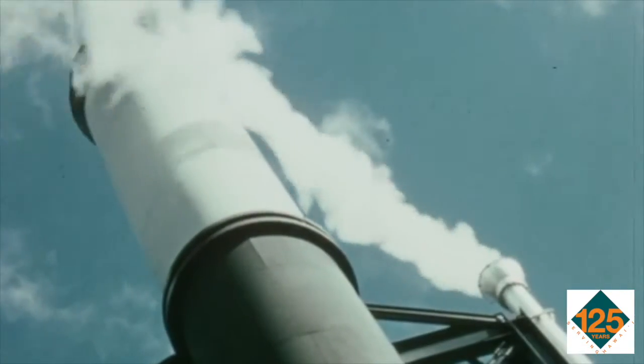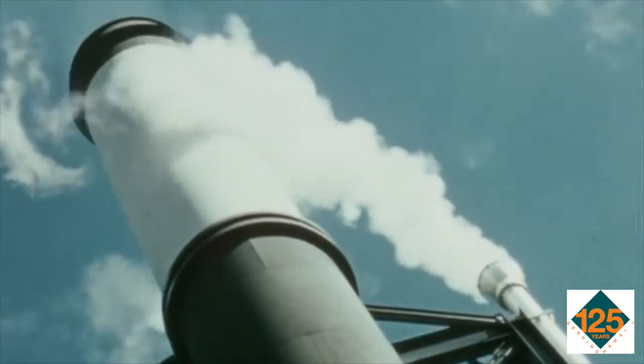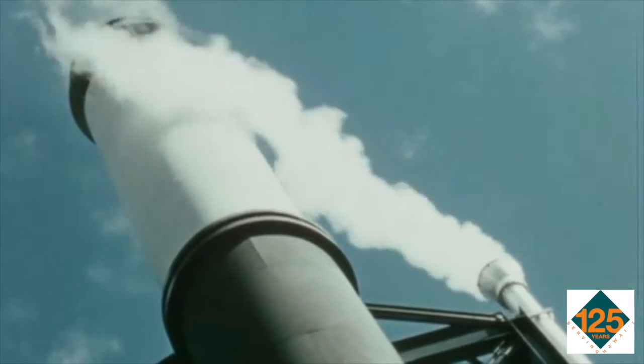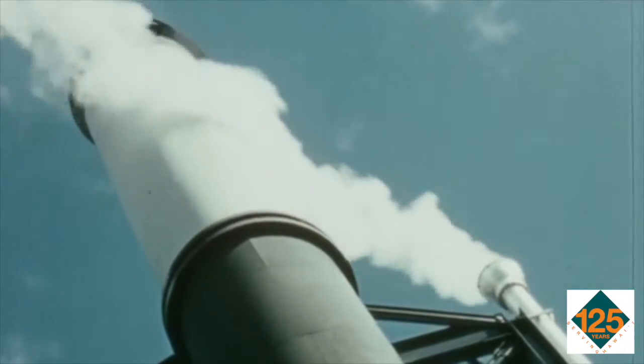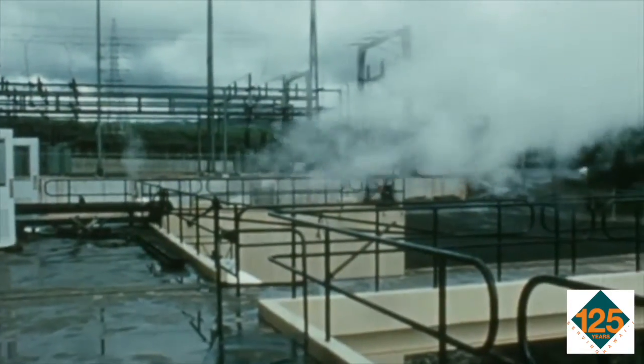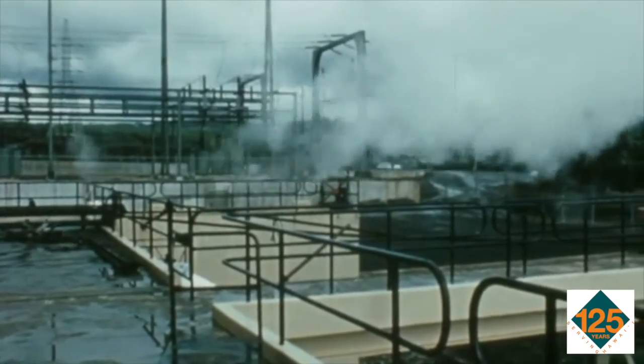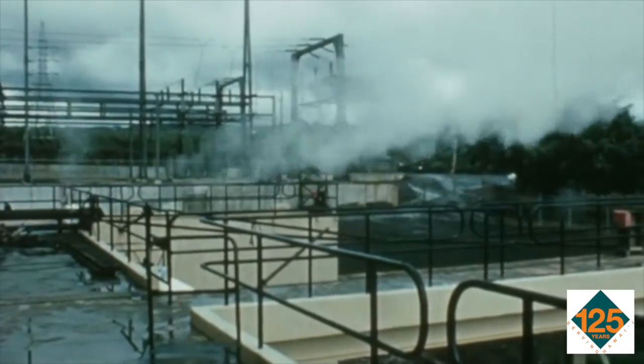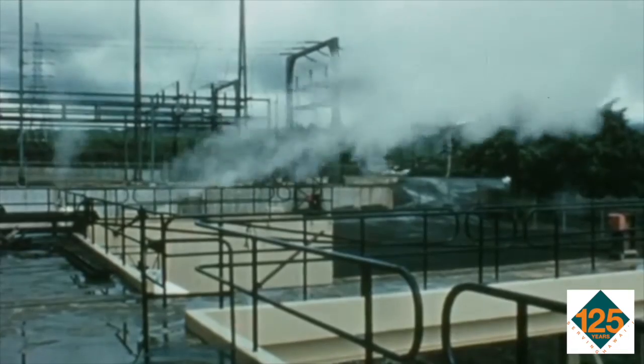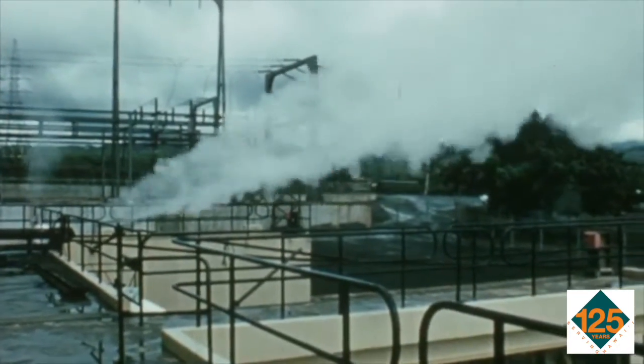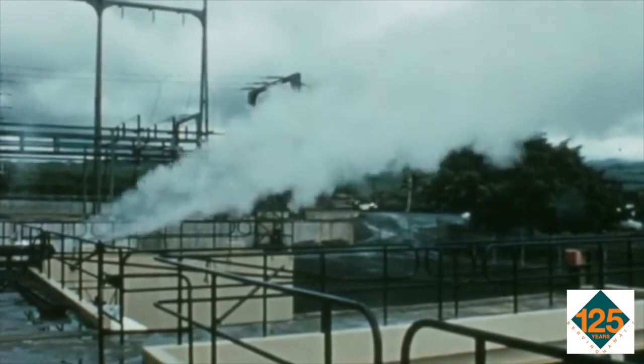And now the boiler was ready to be fired. The boiler was put through rigid tests and exacting cleaning operations, which included blowing the main steam line. This minimizes the possibility of damage to the turbine by removing foreign matter from the piping system, which might blow in with the steam.